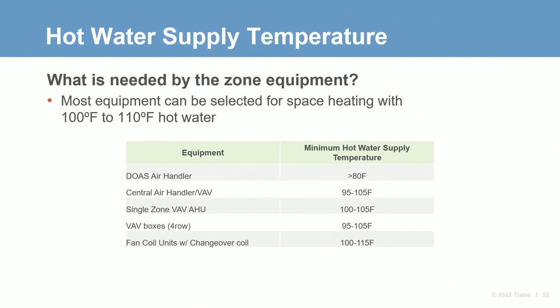This table shows typical hot water requirements for different equipment and system types. These temperatures will likely surprise many people. They are much lower than common design conditions we typically see. But any coil selection program will be able to confirm that these temperatures are achievable today. And the one and only John Murphy is going to dive deeper on this specific topic on a future EN, so keep an eye out for that.